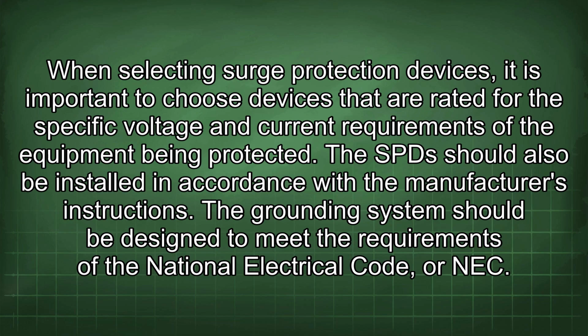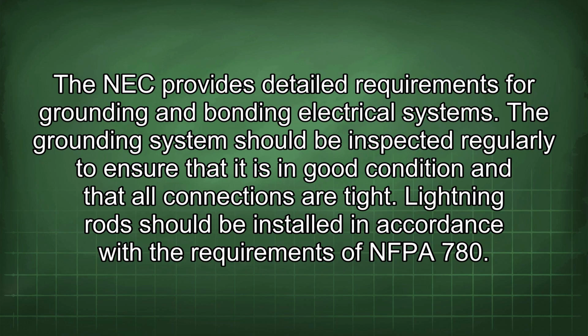When selecting surge protection devices, it is important to choose devices that are rated for the specific voltage and current requirements of the equipment being protected. The SPD should also be installed in accordance with the manufacturer's instructions. The grounding system should be designed to meet the requirements of the National Electrical Code, or NEC. The NEC provides detailed requirements for grounding and bonding electrical systems.